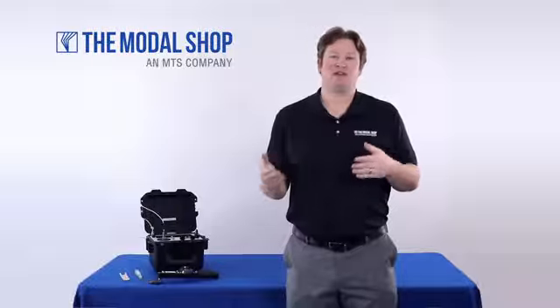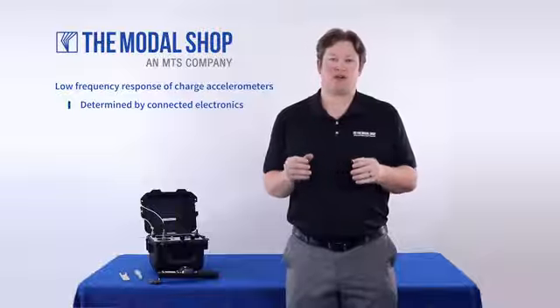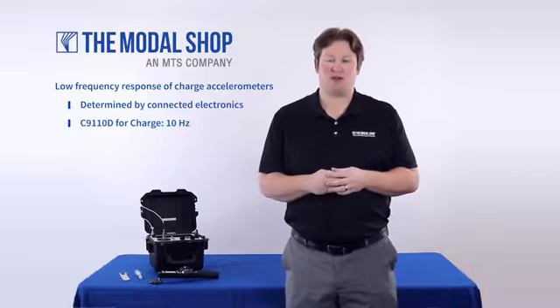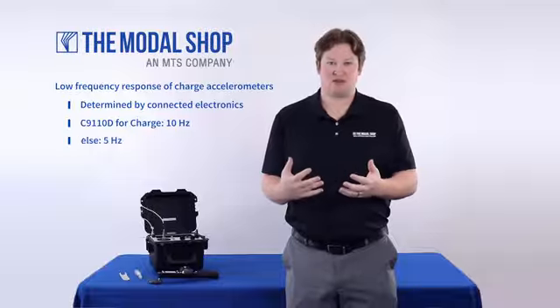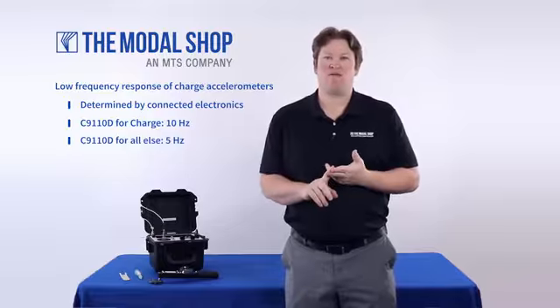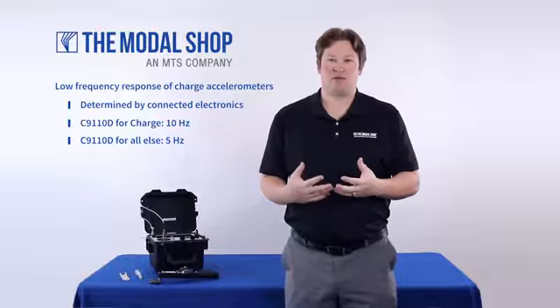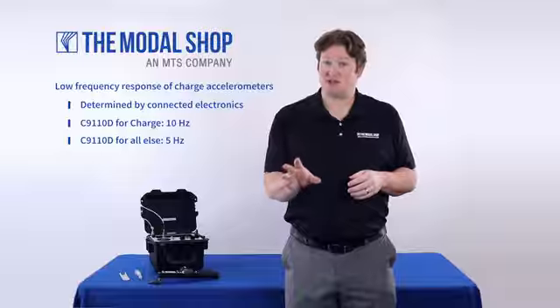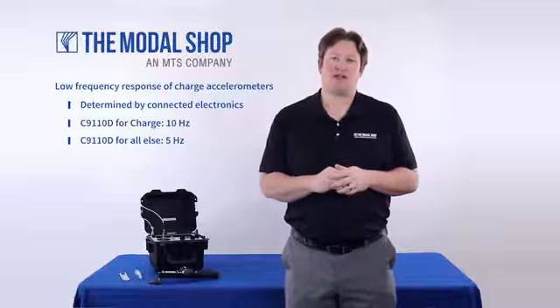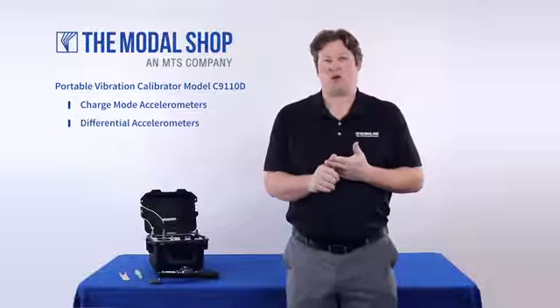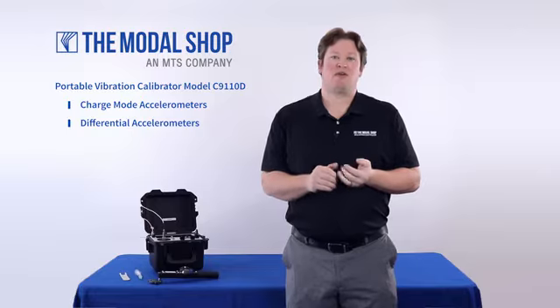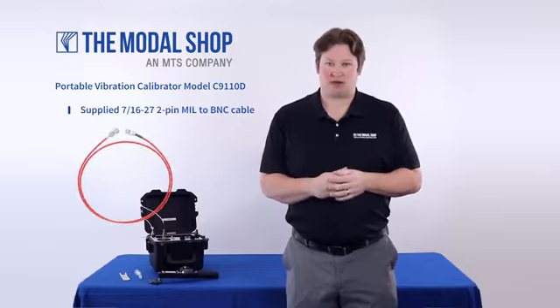You might be wondering, what's the low frequency response of this transducer? Well, the low frequency response of a charge mode accelerometer is determined by the electronics that you connect it to. In this case, the low frequency limit of the C9110D when calibrating a charge mode accelerometer is 10 Hz. For all other sensor types, ICP, voltage, modulated current, the low frequency limit is 5 Hz. Now that was a single-ended charge mode accelerometer commonly found in test applications, but the C9110D also works for differential accelerometers that you find on turbine engines in aerospace or the energy market, and it's supplied with a cable that mates to the most popular transducers in those markets.